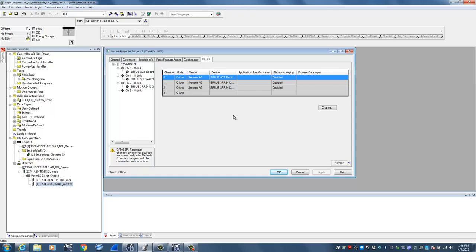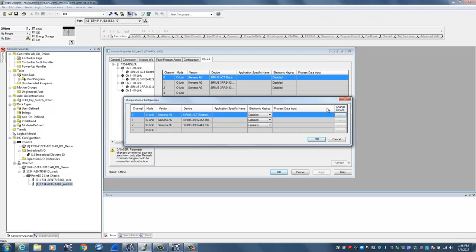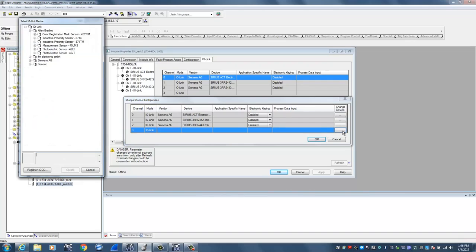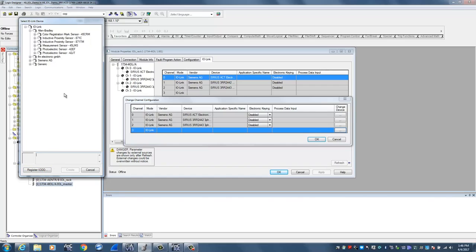If I was to try and add a fourth device, it's as simple as clicking on the change button here and in the lower right-hand corner click on the button with the three dots. It'll open up a catalog for all your registered IO-Link devices. If the device that you want to add is not in the list, it's as simple as coming down here and clicking on register IO-DD. Go out to your hard drive and select the IO-Link device description file and register it. Once it's registered, it becomes an available choice in this catalog.